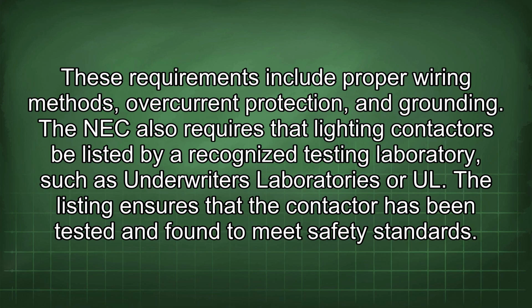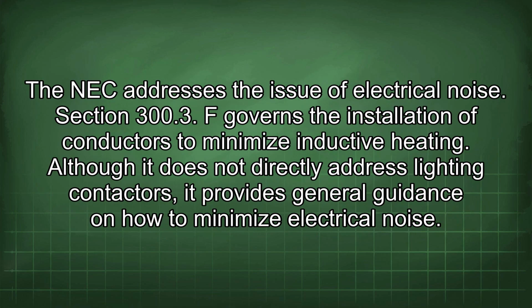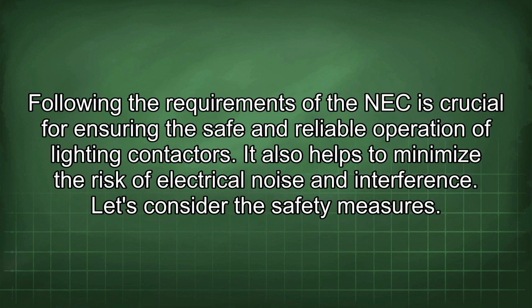The NEC also requires that lighting contactors be listed by a recognized testing laboratory, such as Underwriters Laboratories or UL. A listing ensures that the contactor has been tested and found to meet safety standards. The NEC addresses the issue of electrical noise. Section 300.3 F governs the installation of conductors to minimize inductive heating. Although it does not directly address lighting contactors, it provides general guidance on how to minimize electrical noise. Following the requirements of the NEC is crucial for ensuring the safe and reliable operation of lighting contactors. It also helps to minimize the risk of electrical noise and interference.